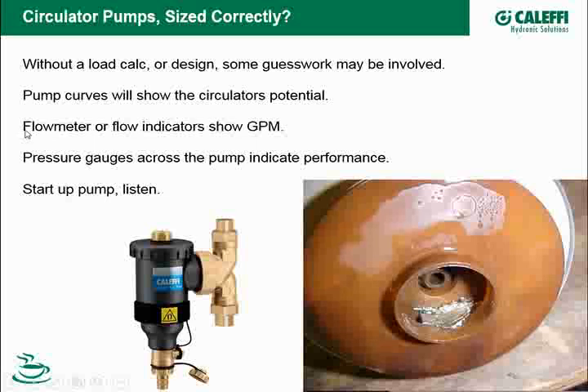Another handy gauge you put on a system is a flow meter that'll tell you. We've got a little 132 flow meter that you can just pull a ring and you can see what this pump is doing. So if you know your system needs 10 gallons a minute through it, if you've got a flow meter or a flow setter somewhere on the job, you can just confirm that's in fact what's going on. You can do it with pressure gauges. We're going to show you how to do that in the webinar that we're going to do in December with John Siegenthaler. He's going to show you how to check pump performance with pressure gauges as well as flow meters and stuff like that.